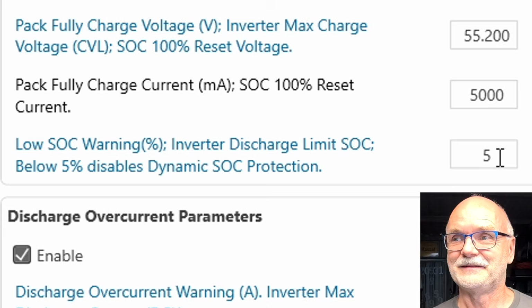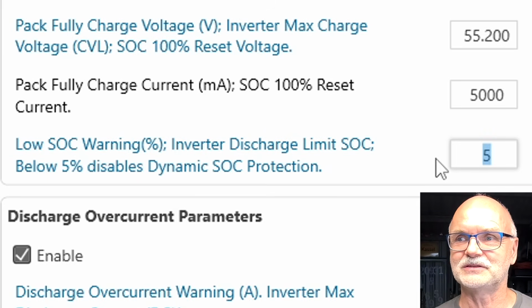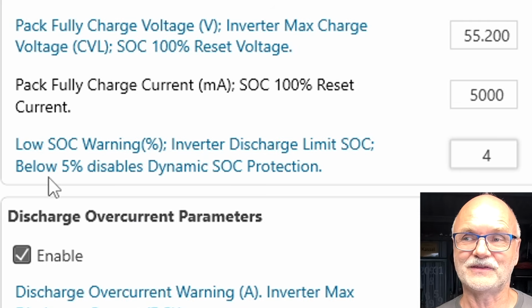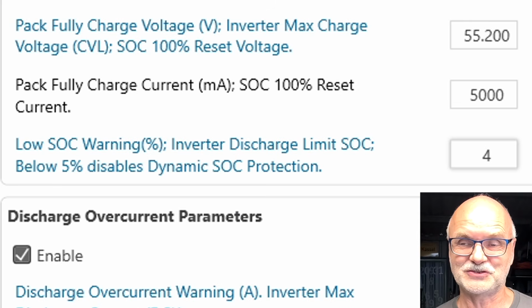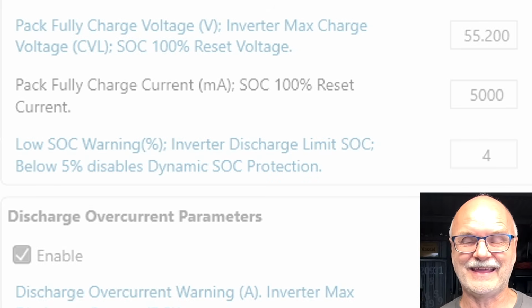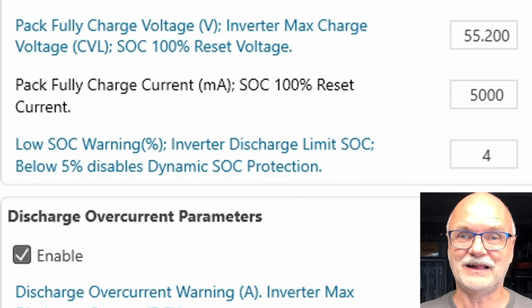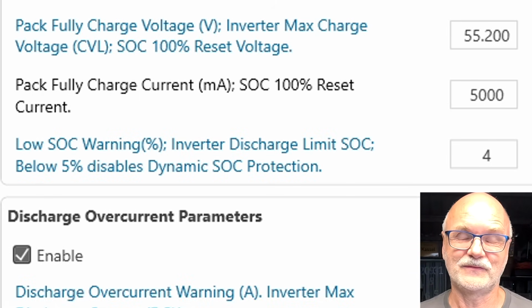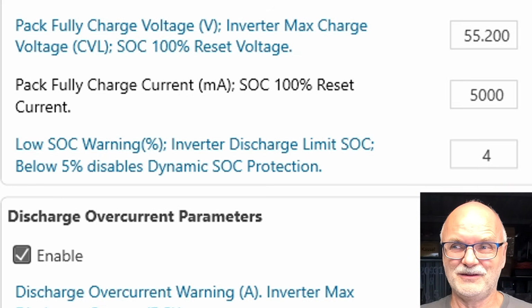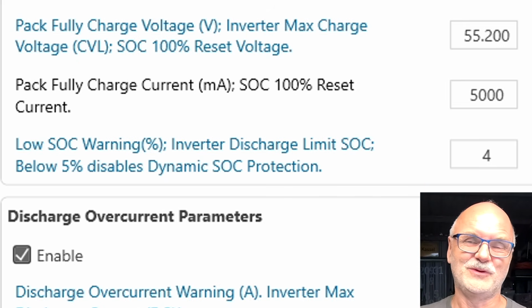No grid, DCL is 0, inverter turns off, but your battery is at 70% state of charge and you will not be able to use this energy. So as good as this idea is, it doesn't work in real life, neither for me nor for everyone else. So what you have to do is change this to 4%, because it says below 5% it disables this dynamic state of charge protection. Unfortunately, we have to set this to 4%. I cannot have DCL 0, and no one else should either, because if the grid fails, you are in the dark. This is probably the first time they've introduced such an idea to a BMS algorithm, which isn't bad, but the actual mechanic doesn't really work.